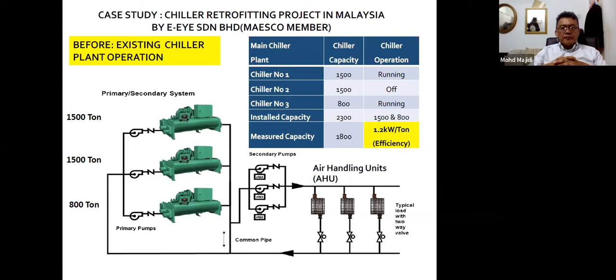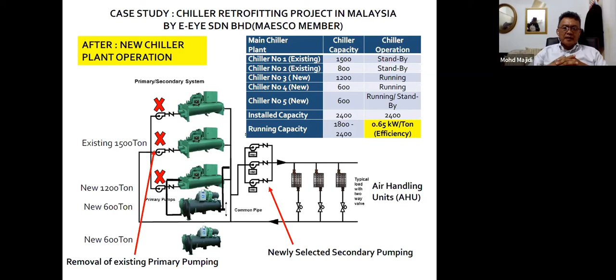By installing 3 new chillers and removing one of the 1,500-ton chillers, the installed capacity increased to 2,400, while the actual running requirement could be addressed at either 1,800 or 2,400 tons. The new effective efficiency was 0.7 kilowatt per ton. One of the key things also done was eliminating the primary pump at the chiller end, which provided a tremendous saving to this site.